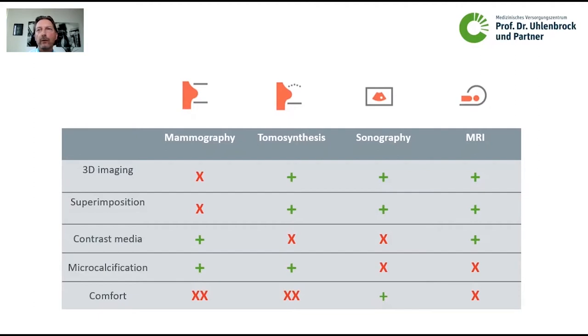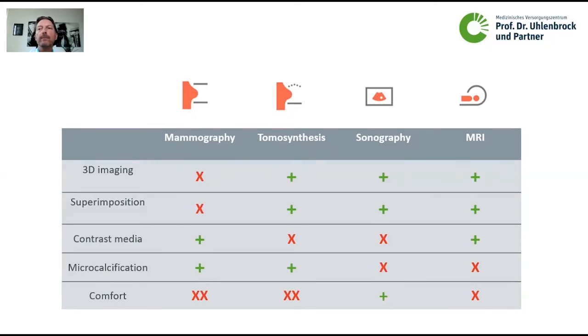Secondly, tomosynthesis. This is going into 3D, at least using systems which do a 50-degree sweep of the tube. We get rid of the superimpositions, and we can't use contrast media. We have a good look at the microcalcifications, likely better than in mammography. But as in mammography, we have a problem with comfort due to the compression of the breast.